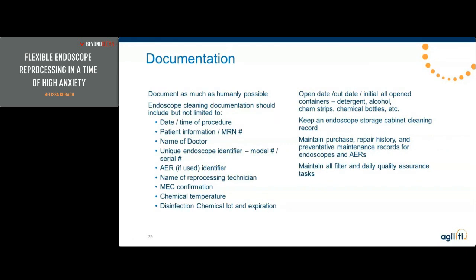But there's also a different mentality between sterilization and high-level disinfection. When you're sterilizing, it is usually about how those instruments were sterilized prior to use in the OR. But when you're talking about high-level disinfection and flexible endoscopes, it's really about that patient's bioburden within that scope and the cleaning load run after that. So it's a whole different mentality on how you look at that scope and that documentation.